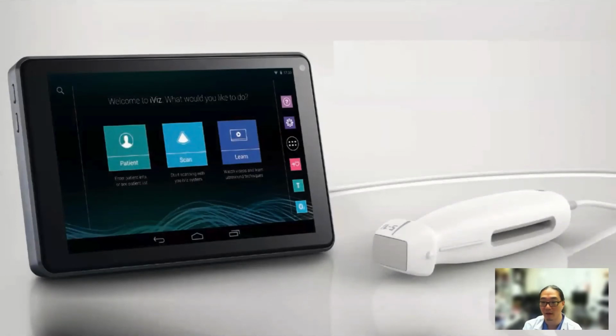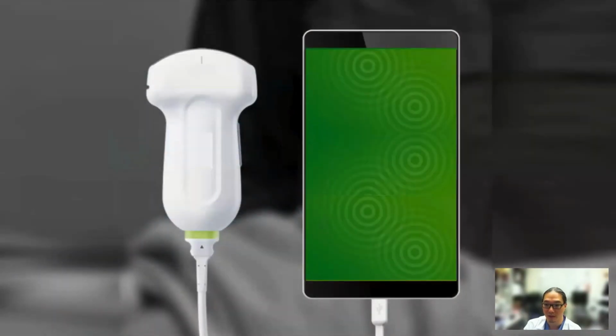Or do we use a probe with a proprietary display device, in which case it's easier to separate the two. So if one breaks, I can get one replaced and repaired while the other part still functions. But these are going to be a little more expensive because they're proprietary devices. So, as a medical device, those display items are going to be a little more expensive. They are going to be a little more rugged and probably a little more durable than some of the consumer products. Or do we go to a non-proprietary device with software where I can just load the software, do the scanning with the probe, and have that non-proprietary device, which is a consumer level, probably much easier to replace and harder to maintain because it's a little more fragile. And then you're also now responsible for all the software updates for the operating system for that.